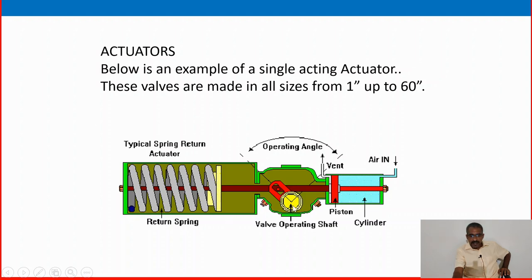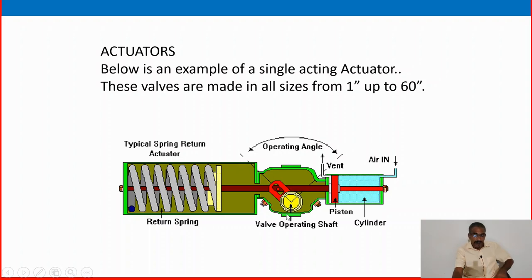You can see the return spring, open position and closed position, air in and vent, and piston and cylinder. When air is in — air to open valve — air in means the valve will be in open position. When the air is released or air fails, the valve will be in closed position. At the top there is an indication showing whether the valve is in closed or open position.